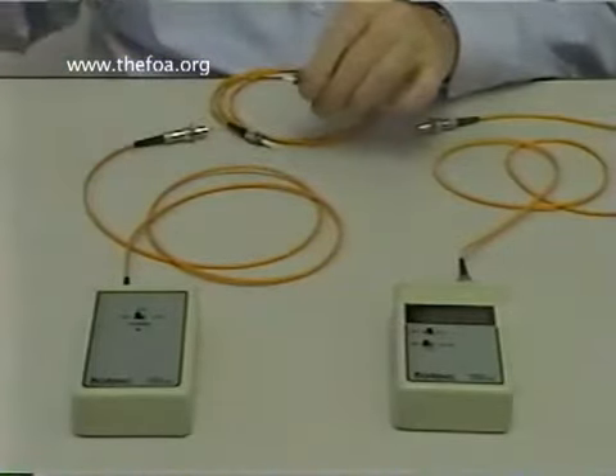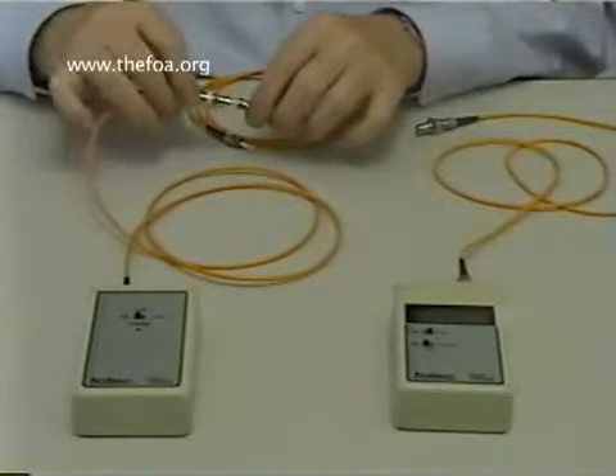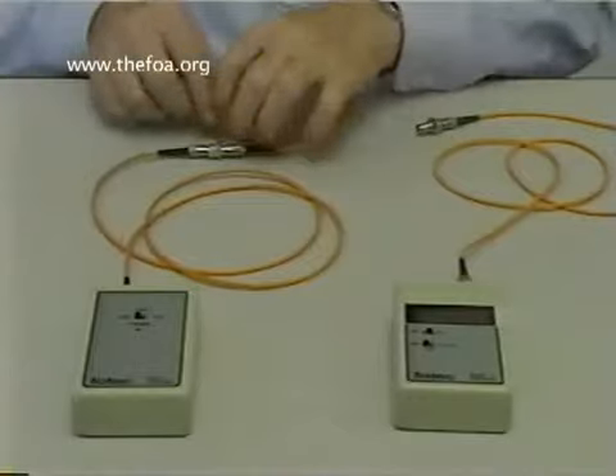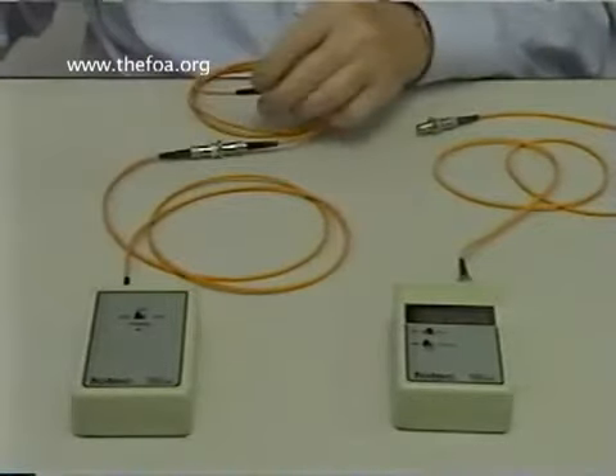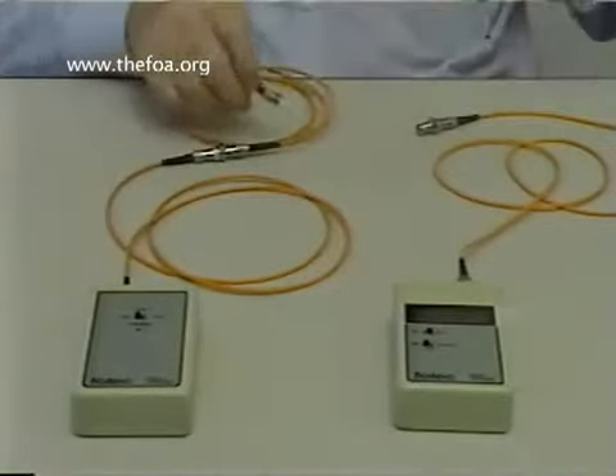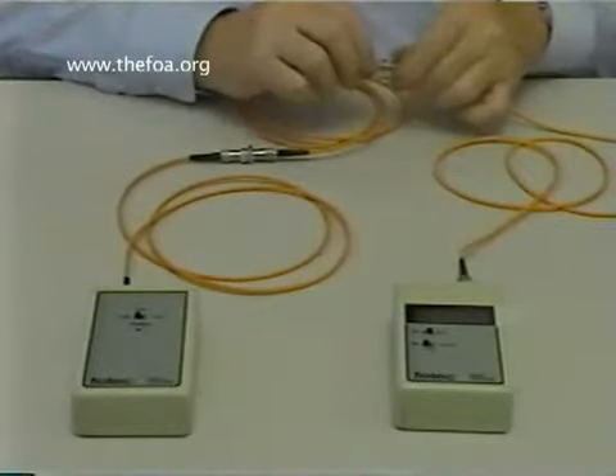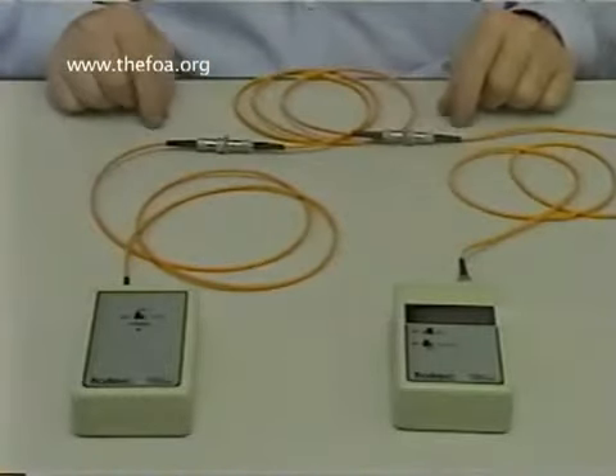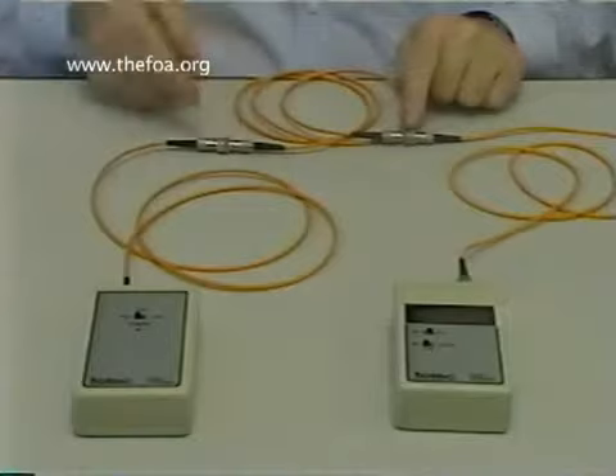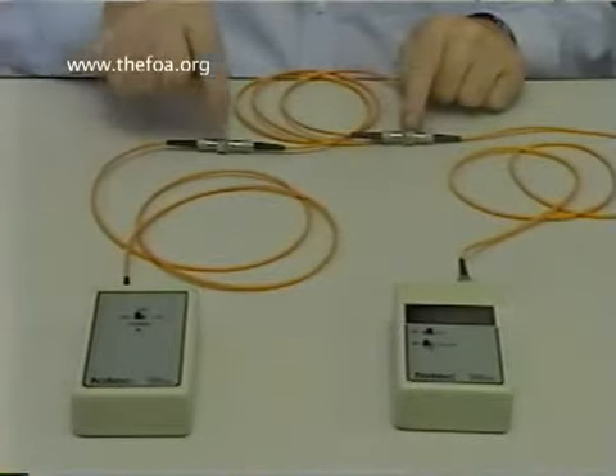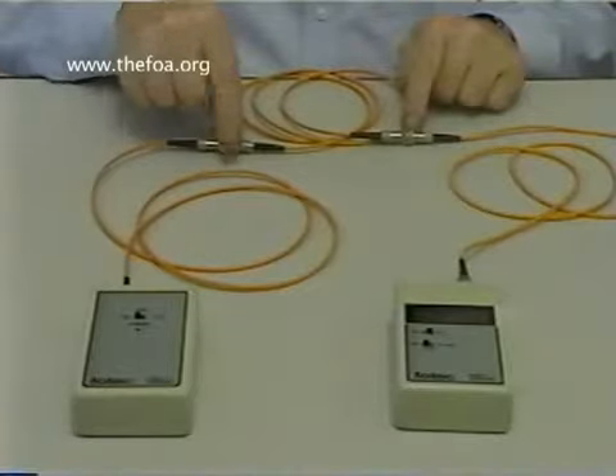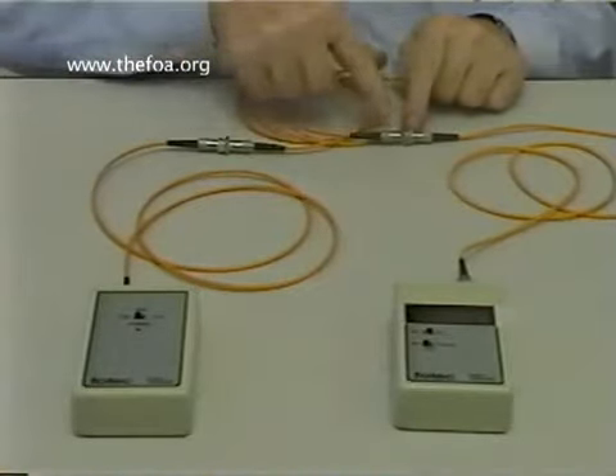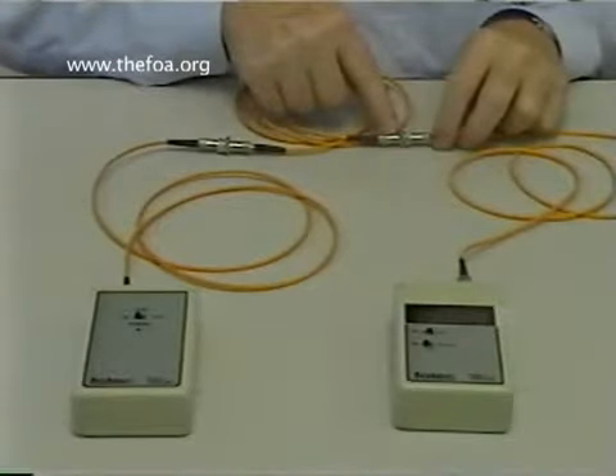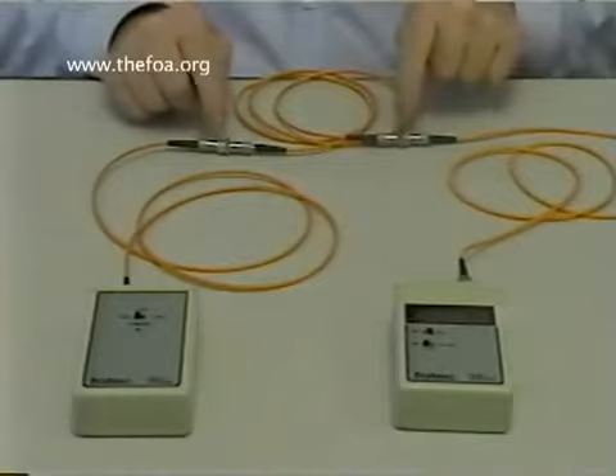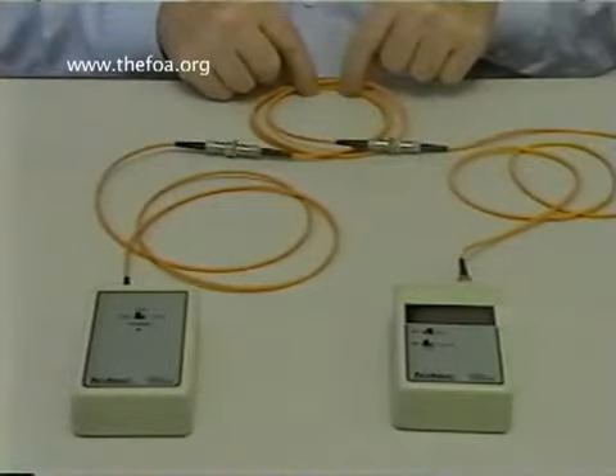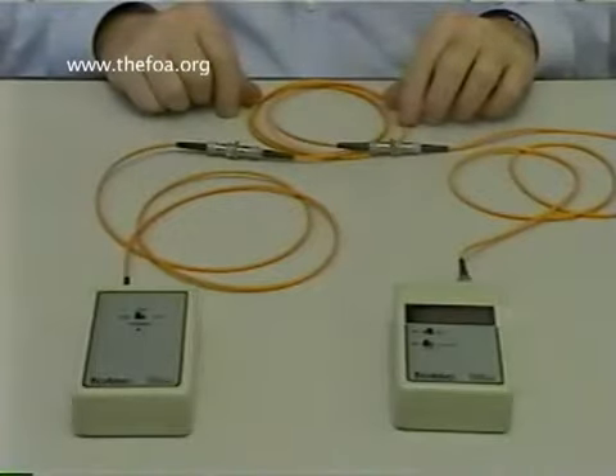So here's another cable. We'll take the dust cap off, clean the connector, attach it to our launch cable, take the dust cap off the other side, clean it, attach it to our receive cable. Now, what we're testing is the connectors on both ends. We know how much light is coming out of our launch cable. We have a loss here in this pair of connectors. We may have loss in this installed cable, and then we have loss in the second connector that's attached to the meter. So we're measuring the loss of both connectors and anything which might be lossy in between, like, for example, a long length of cable.